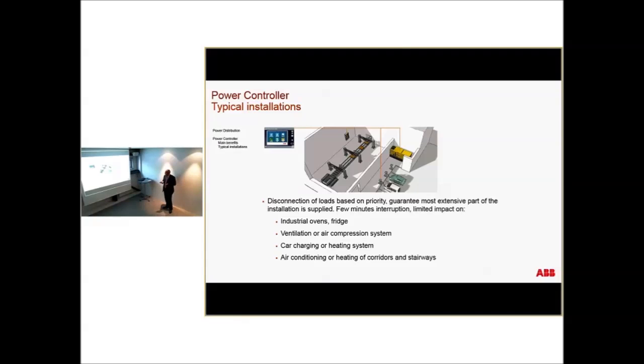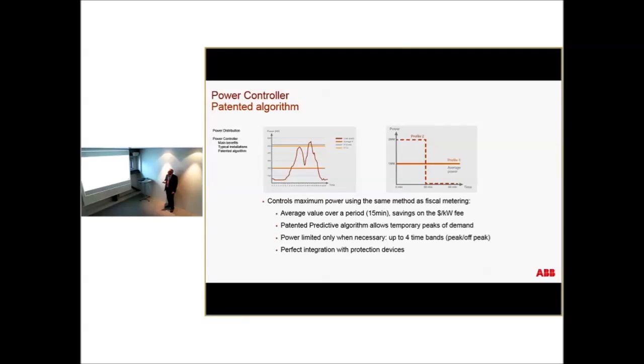There are some examples here, like industrial oven, ventilation, car charging, air conditioning, something non-essential. You can disconnect it and avoid the peak on the consumption. This is an example. If you decide to avoid this peak, you decide here which load you want to disconnect. Basically, it also gives quite good flexibility because you have 4 time bands, and the integration is inside the release.